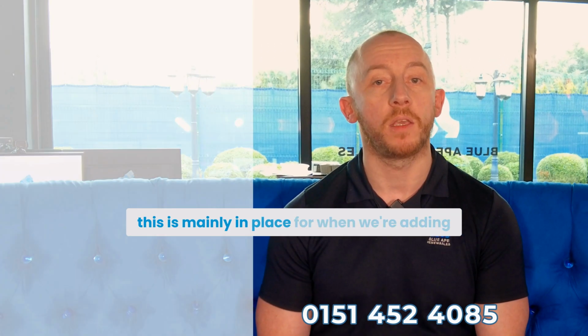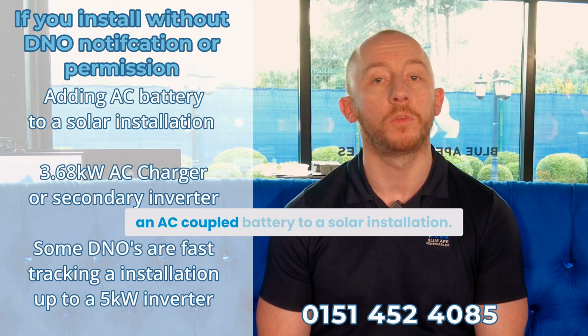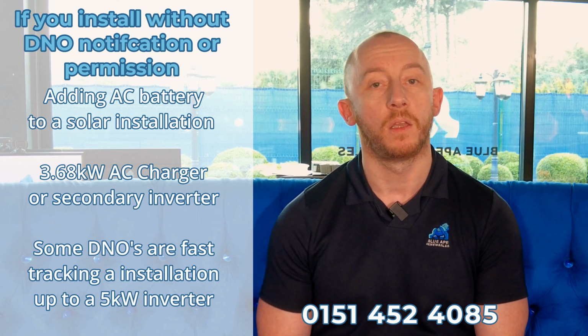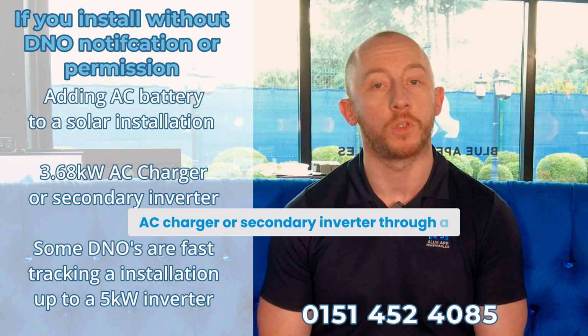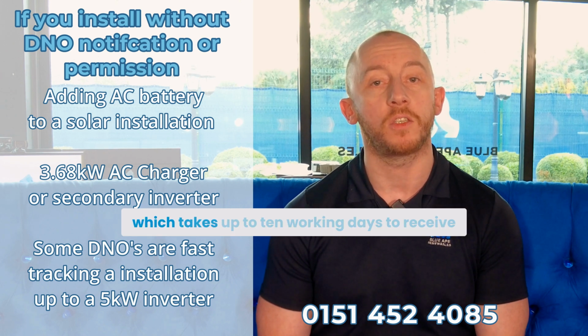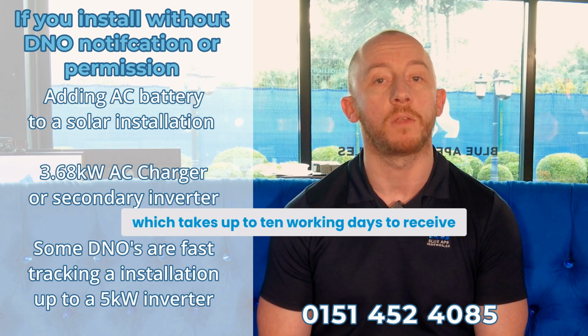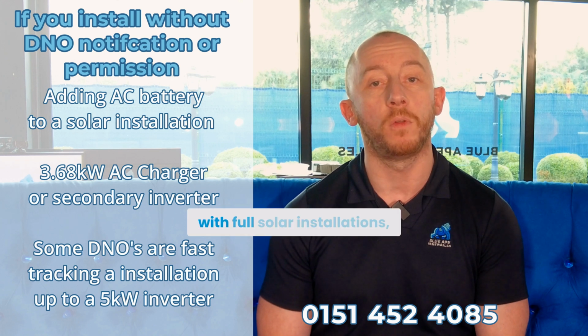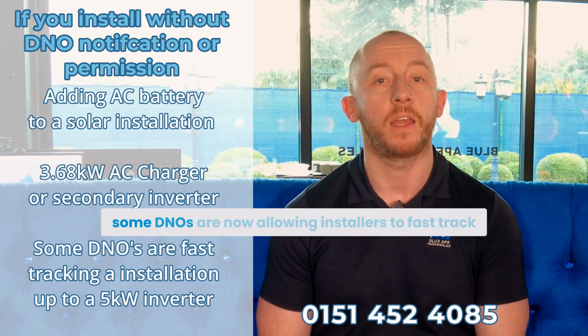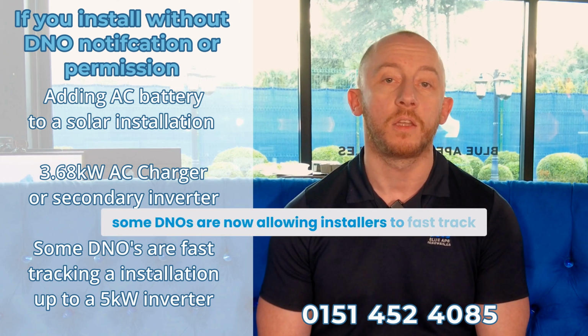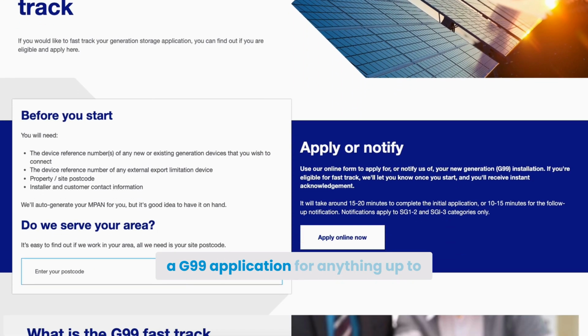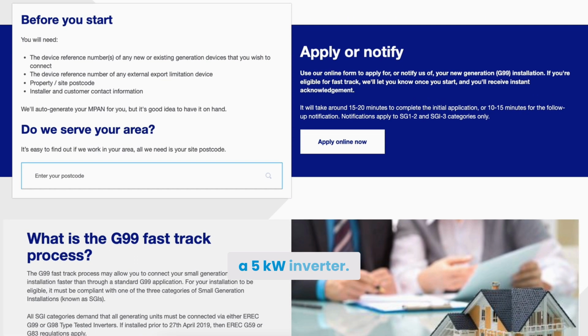This is mainly in place for when we're adding an AC-coupled battery to a solar installation. Generally, you're permitted to install a 3.68 kilowatt AC charger or secondary inverter through a G99 Fast Track, which takes up to 10 working days for a response. However, with full solar installations, some DNOs now allow installers to fast track a G99 application for anything up to a 5 kilowatt inverter.